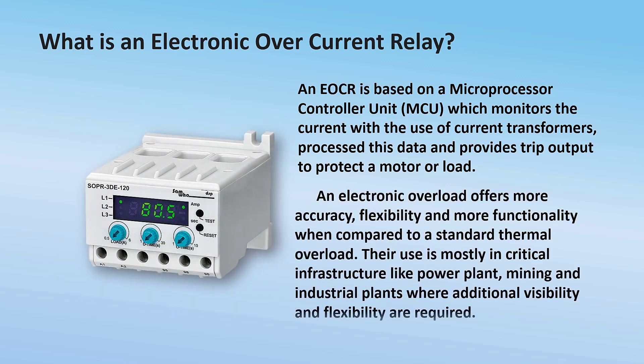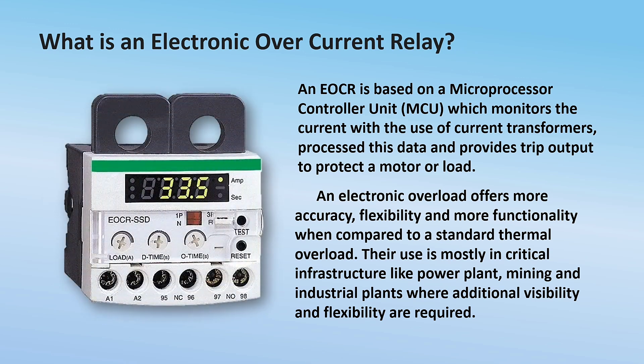What is an electronic overcurrent relay? An EOCR is based on a microprocessor controller unit or MCU, which monitors the current with the use of current transformers, processes this data, and provides trip output to protect a motor or load. An electronic overload offers greater accuracy, flexibility, and more functionality compared to a standard thermal overload. Their use is mostly in critical infrastructure like power plants, mining, and industrial plants where additional visibility and flexibility are required.